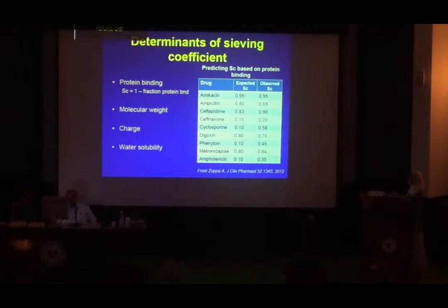Well, for hemofiltration, it also depends on whether it is a post-dilution mode or a pre-dilution mode, because in the post-dilution mode, the saturation is 100%, and in this case, the formula goes like we mentioned. Clearance of the hemofilter is going to be equal to the ultrafiltration flow rate multiplied by the sieving coefficient.